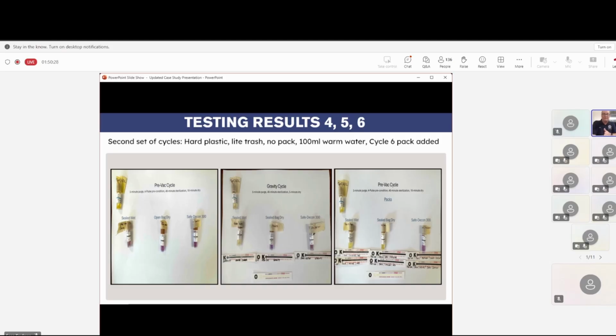When I get to cycle 6, I put the pack in, and this was the denser pack. This is the one I taped literally down hard on both sides. And these are 40-minute cycles, by the way, 4 pulse. Again, I ran 4 pulses, not 3. You'll see that with 5% trash on the pre-vac cycle with the denser pack, this is what I ended up with. On cycle 6, both bags did rupture. When they rupture, I'll show you a picture of what they look like, but they did blow open. The problem is when do they blow open? If they blow open on 3 or 4, it's not enough to be able to get that steam and heat to actually penetrate, and it's going to act just like a gravity cycle. Next slide, please.